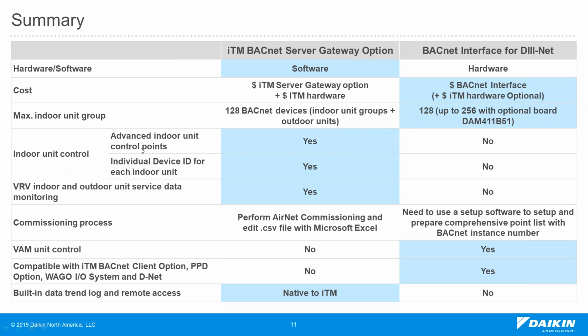As far as the indoor unit controls, the ITM gateway definitely has more advantage because it provides advanced indoor unit control points that can make use of ITM's native logic, and it also has this virtual BACnet router function to assign individual device IDs to the indoor units. So for the VRV indoor unit and outdoor unit operational service data, only the ITM BACnet server gateway option can provide this feature and provide those data to the BMS.